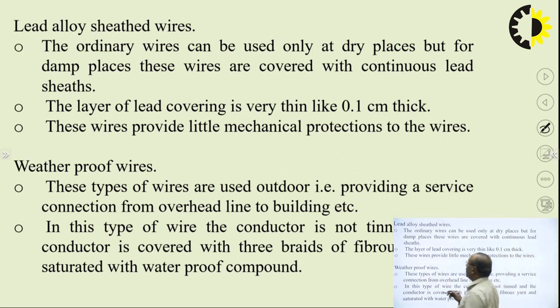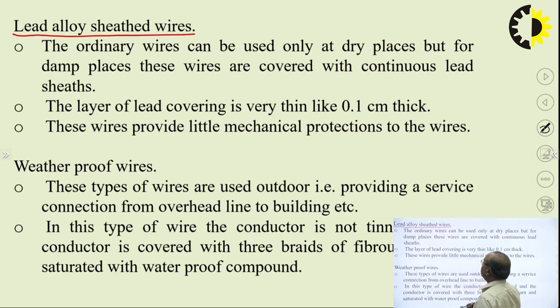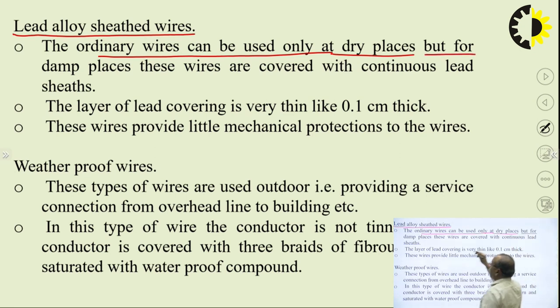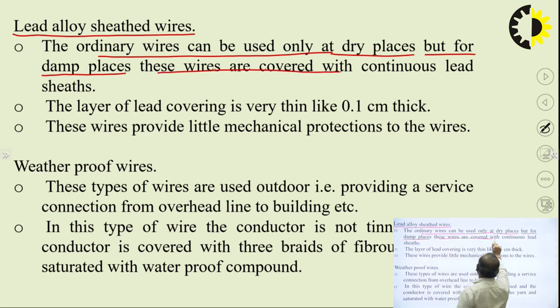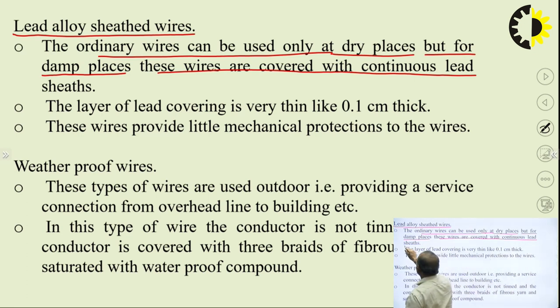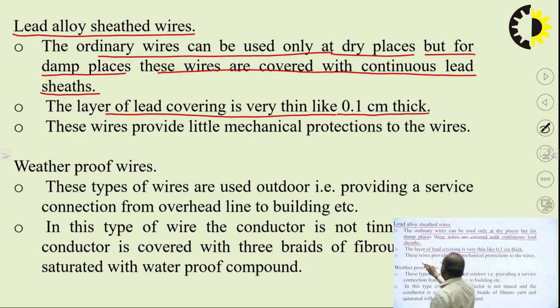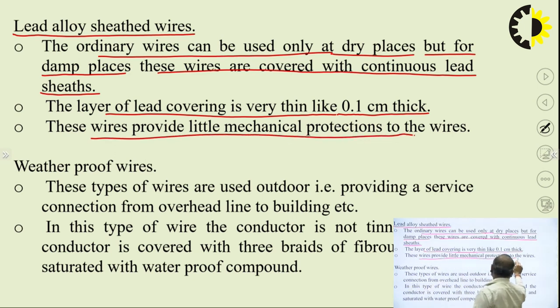The next type is lead alloy sheath wire — another type of insulation. Ordinary wires can be used at dry places where there is no or very little moisture. But for damp places where there is moisture content, these wires are covered with a continuous lead sheath so as to protect from that moisture. The layer of lead covering is very thin, in the range of 0.1 centimeter. These wires also provide some mechanical protection.